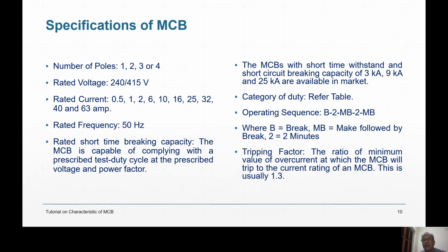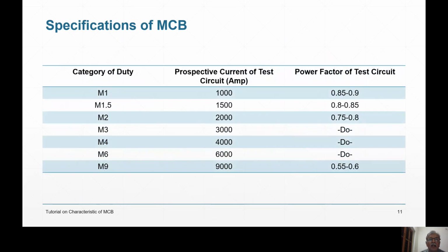Tripping factor is the ratio of the minimum value of overcurrent at which the MCB will trip to the current rating. Usually it is 1.3. That means a 2 ampere MCB will trip at 1.3 times 2, not before that. That is the general understanding. MCBs are available in duty M1, M1.5, M2, like that. What is the meaning of M1? It is designed for prospective current 1000 ampere, 1 kiloampere. M1.5 means 1.5 kiloampere and M9 means 9 kiloampere.